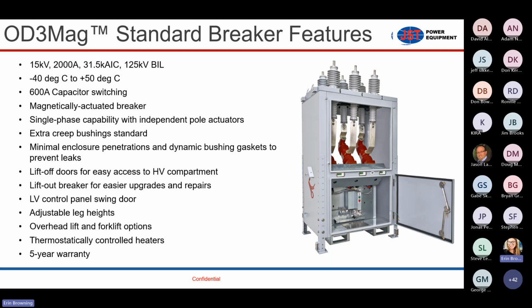So I want to point out that a traditional or a typical circuit breaker spec is going to be 15 kV 1200 amp or 15 kV 2000 amp. Our circuit breaker that you see in this picture is rated for 1200 and 2000 amp. The breaker doesn't get physically bigger if we're talking about a 2000 amp versus a 1200 amp. That's a differentiator between ours and some of the competitors out there. We have a compact footprint for 1200 and 2000 amp breakers.